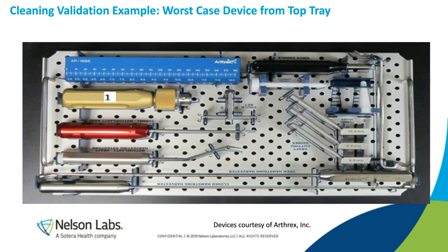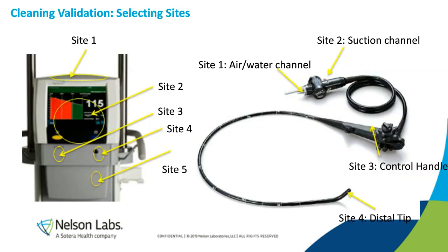There are also challenges that include validation of very large devices. So, for example, on the left, what we look at is different touch points of the device and then comparing those touch points to determine the worst case area to test. Another example of this would be a duodenoscope that is tested for validation.